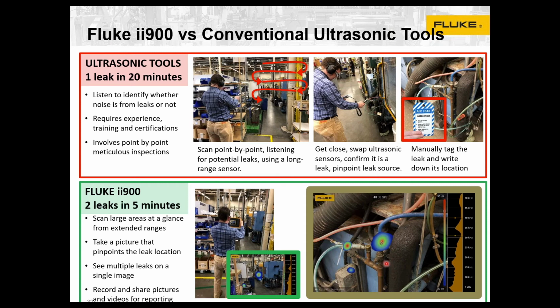There's also a simple tip to distinguish between leaks and reflections. You can actually just change your physical perspective to the leak while keeping the apparent leak on the camera display. Physically move to the left or the right. If the leak stays in the same spot, it's a leak. If it actually moves with you, it's a reflection. So just armed with a few user tips on the camera, you can be up and finding multiple leaks within minutes, as opposed to needing a lot of experience to find maybe one leak in 20 minutes or more. And then, being a newer tool, it gives you the ability to save and document what you're seeing, document leaks for either reporting or to issue a work or repair order.